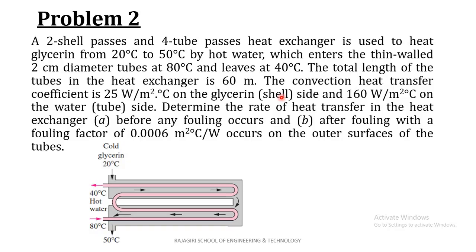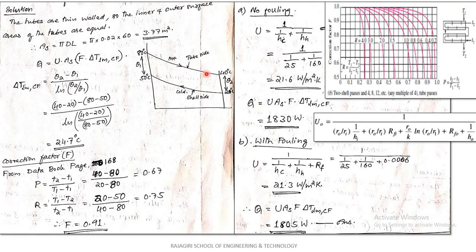Draw the temperature profile for counter flow: water is on the tube side and glycerin is on the shell side. All four temperatures are given. For a counter flow heat exchanger, θ1 = (Th,in − Tc,out) and θ2 = (Th,out − Tc,in). Calculate θ1 and θ2 and the counter flow LMTD, which comes out to 24.7°C.